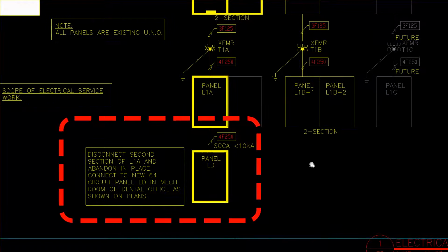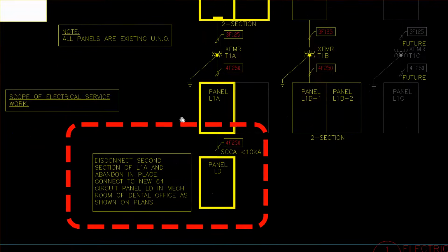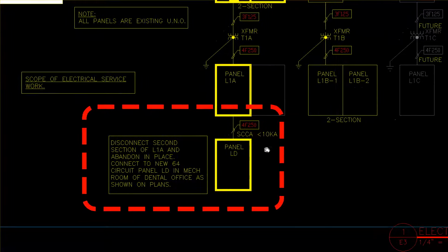Now you'll also see on this particular one, SCCA less than 10 KA. In this particular instance, this is an existing one line, and what's happening is a panel is being added for a tenant improvement to this existing panel. And so 10,000 amps is the lowest fault current rating for any circuit breaker out there of normal commercial use. And so once it's less than 10, usually it's not necessary to put that information on anymore.